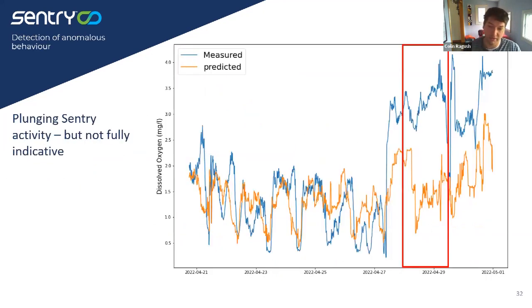Now, models are great for predicting and obviously for process optimization. If you can make a good model, you can run the plant better. The other thing they're really useful for is understanding when processes are changing or problems are happening. Because if you can create a good model that you trust, then when your model doesn't follow the expectations for measurements, or those two aren't close, then you know that something has gone off. So in this case, in the red box, what actually happened was an ammonia and nitrate breakthrough.